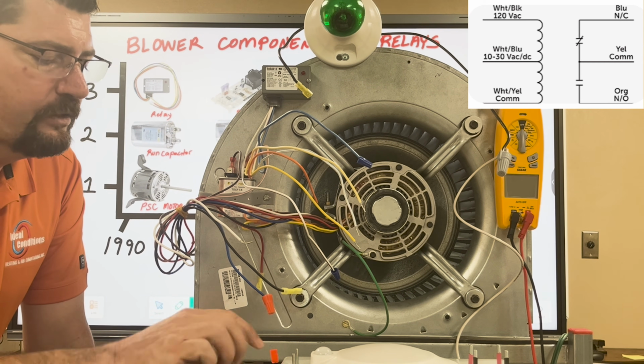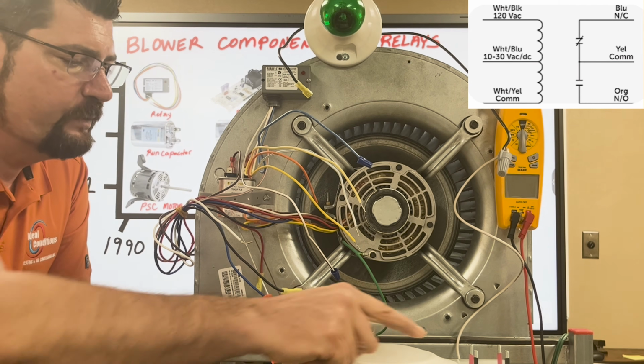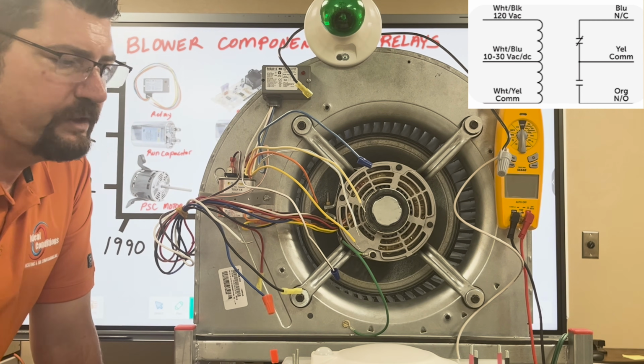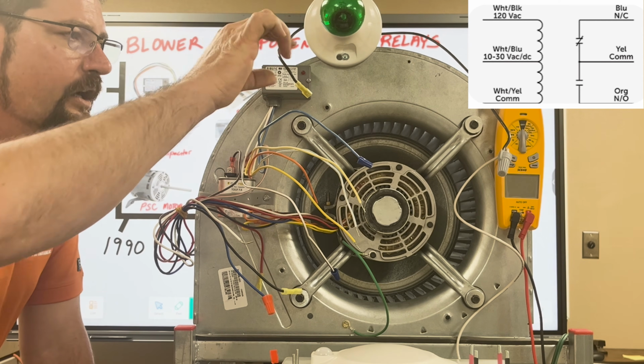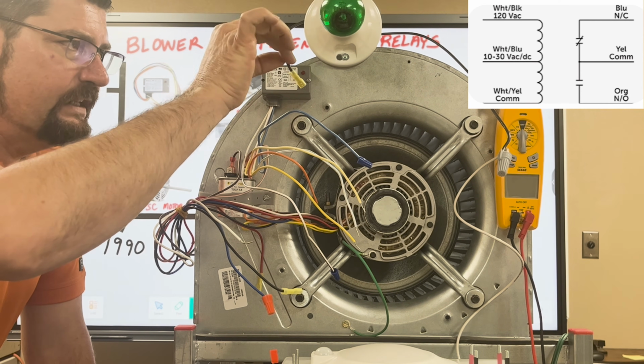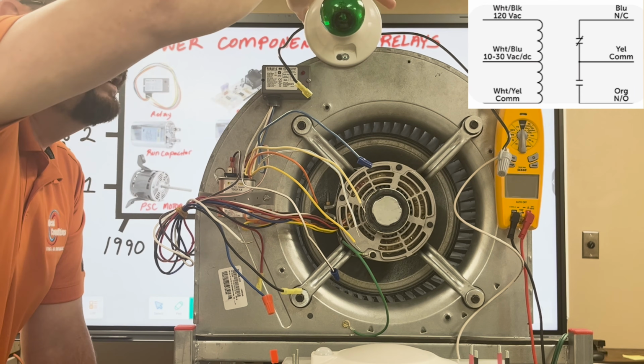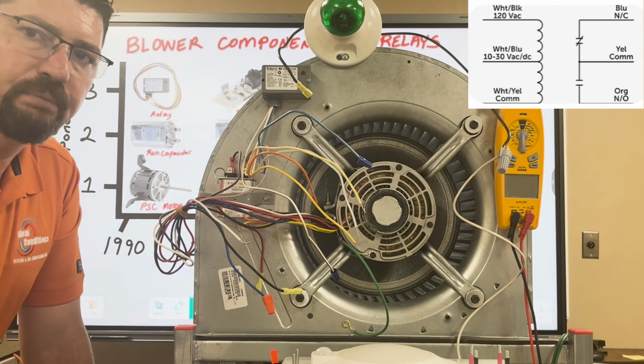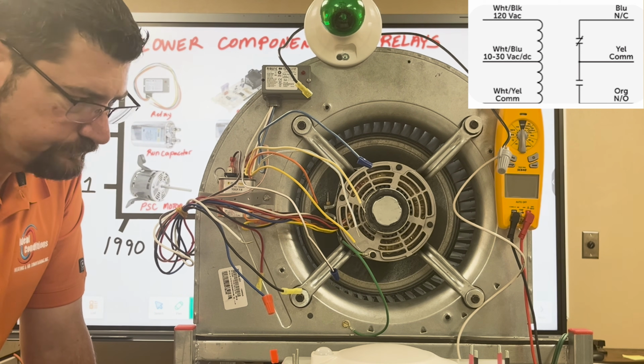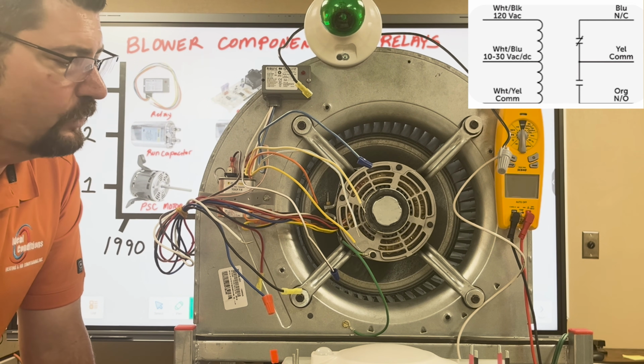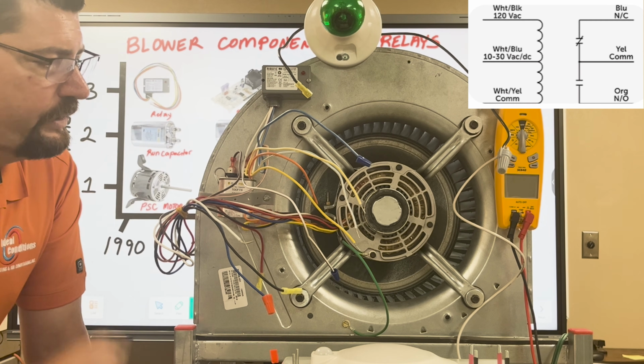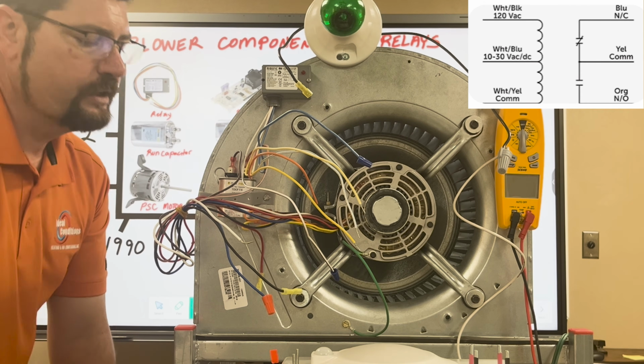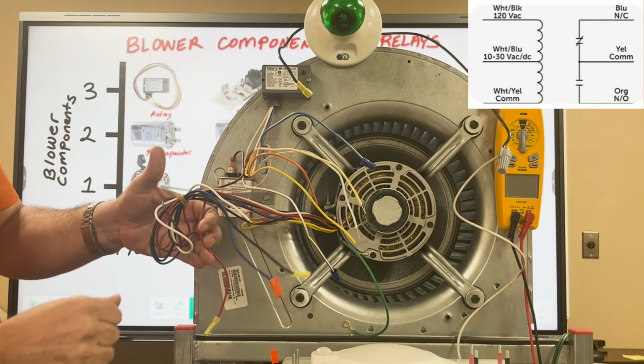We have a power supply here with R and C, 24 volts. We have line voltage over here with the live 240 volts of power. The meter here will show you. If you see the light bulb, talking about the path, we have the high voltage wire going to it. It's not hooked to anything coming out of it. This other black wire has a gray wire nut on it coming to a white wire. That will be plugged into the neutral on an extension cord, so I can provide a path if I want to use 120. The capacitor is pre-wired, and as far as the motor goes, the PSC motor has 3 speeds.